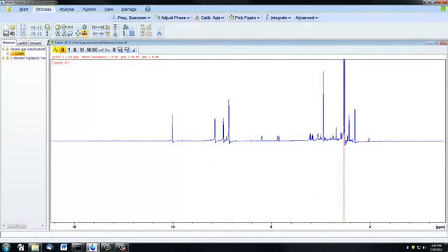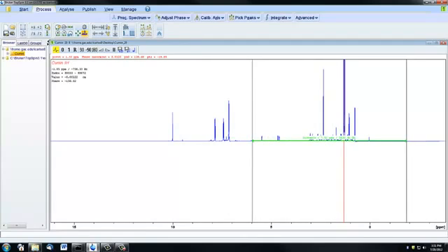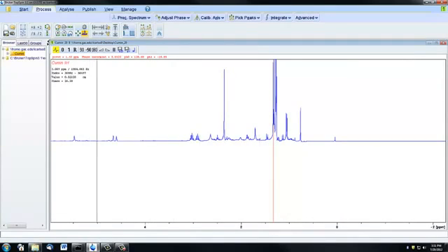And conversely, if you use the downward slope, click that a couple times, and go back and do a first order correction, I'm moving the mouse a lot, but the spectrum is not moving very quickly. So it can be helpful to use the coarse adjustment first and then maybe zoom in. So here I can show you if I zoom in on this part of the spectrum, maybe do some coarse adjustment first, and then when it looks pretty good to me, I might switch to a finer adjustment and just try to really make small little changes in the zoomed in version.